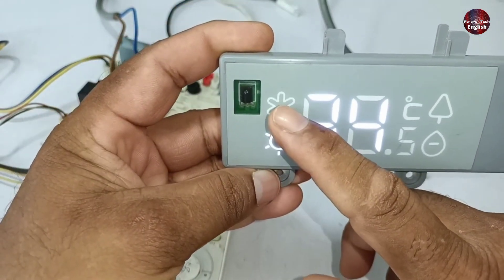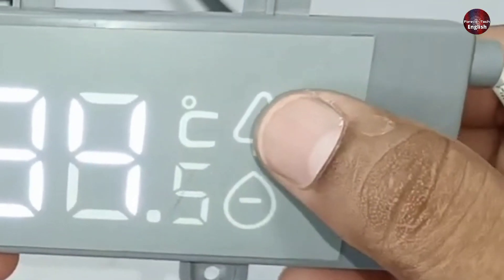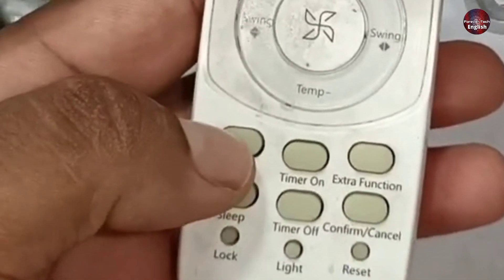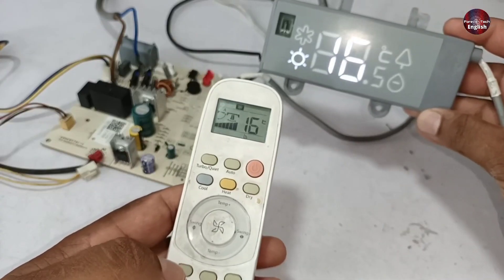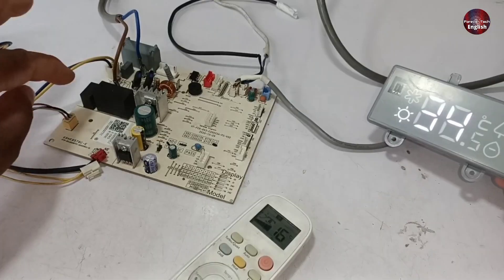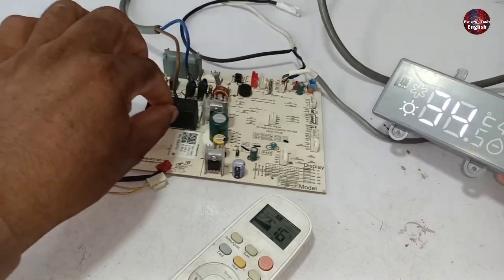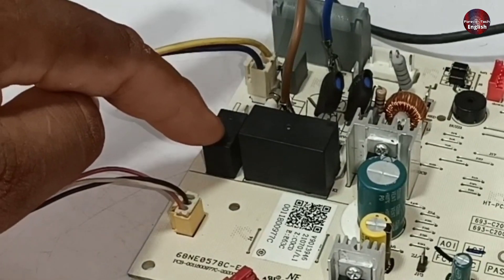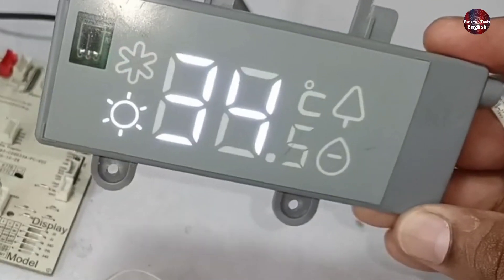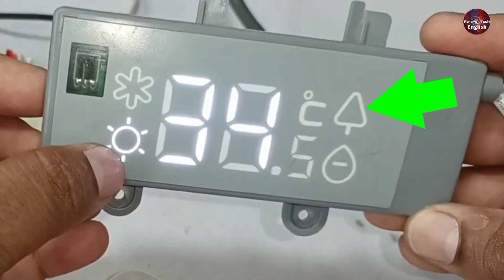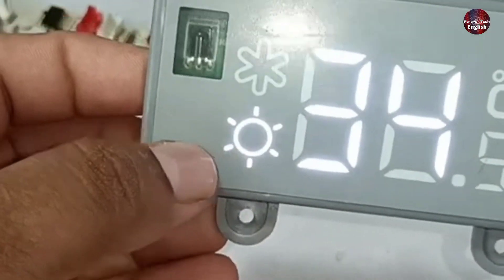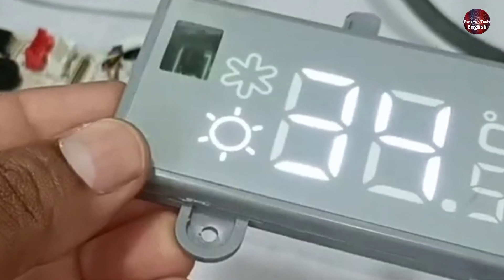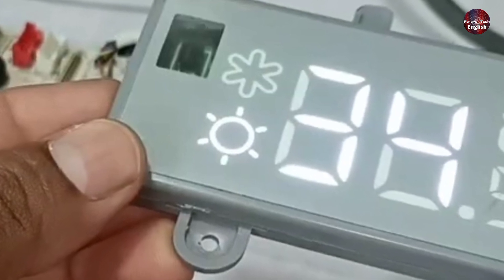The upper light indication is for cool mode. This light indication is for the health function. I will press the health button on the remote. As I press the health button, I heard the switching sound from the circuit board — this is the switching relay for the health function. However, the display does not show the indication for the health function. The display is stuck on heat mode and indicating only heat mode.